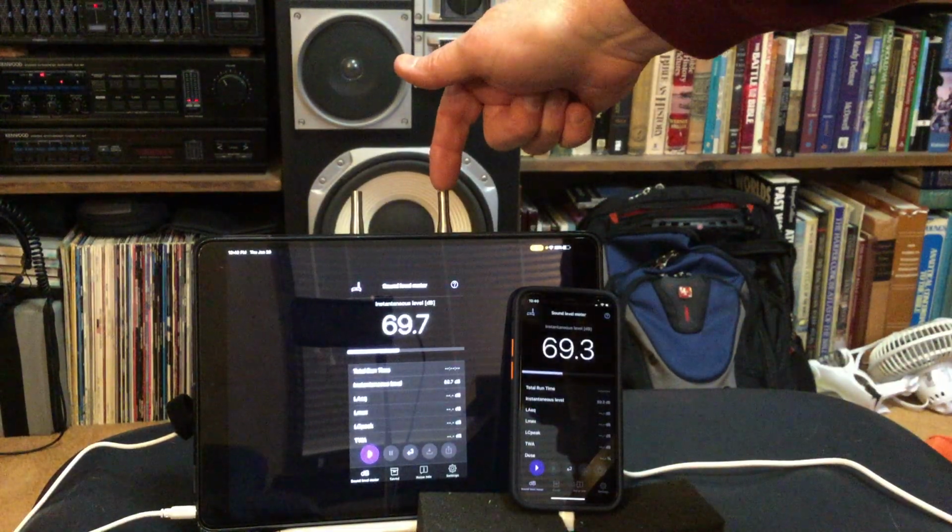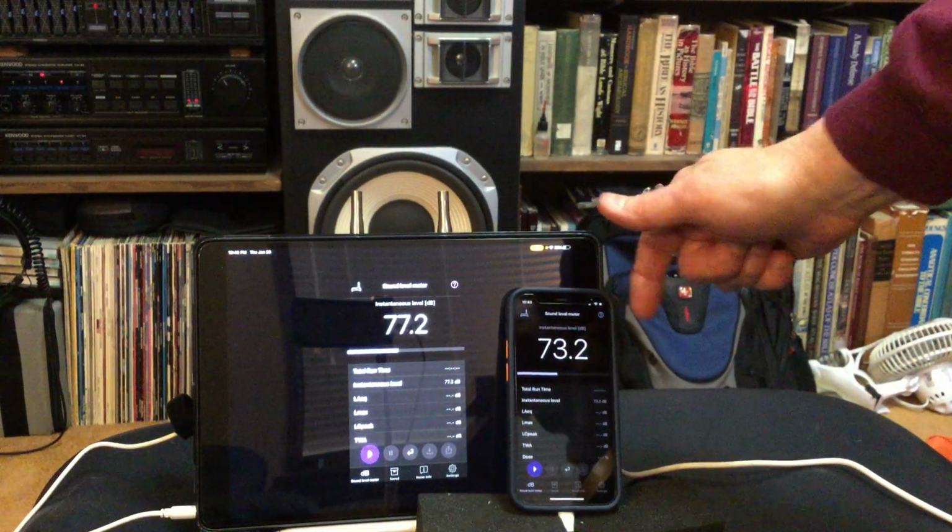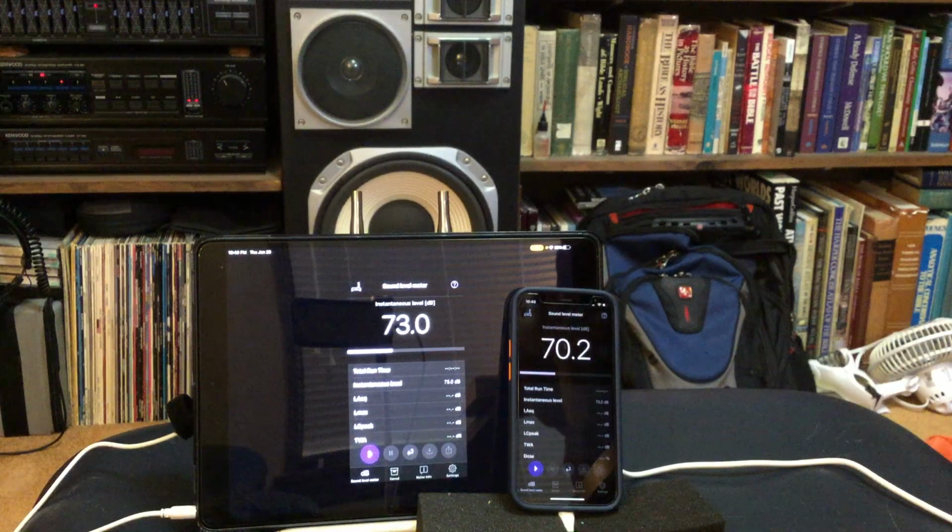The right microphone is connected to my iPhone, also running the NIOSH app, and I calibrated it to 94, and I double-checked it at 114. And I'm going to just try to compare the two levels and see how accurate the two devices with the two calibrated microphones are. So I'll stop talking in a moment, just let it go quiet, and then I'll put some noise on.